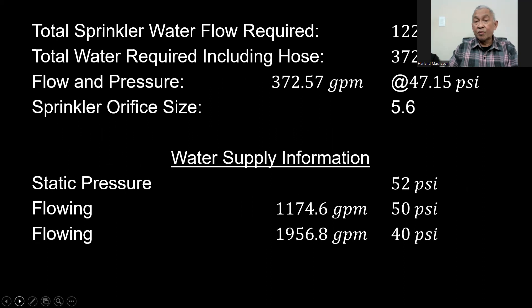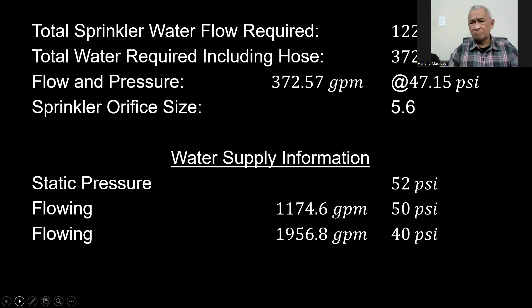The total sprinkler water flow required is 122.57 GPM, and adding the hose allowance of 250 GPM, the total water required is 372.57 GPM. Based on our hydraulic calculations, the result would be 47.15 PSI at 372.57 GPM with a sprinkler orifice size of 5.6.